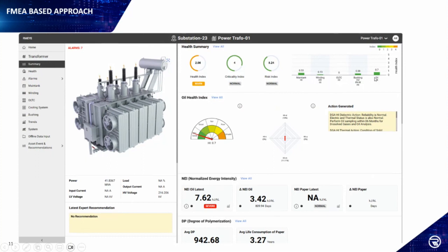The health score of these components is calculated using different parameters. Those parameters I have listed down for the winding, taking it as an example, are the ones we used. Again, this is just one set of parameters. There are other sets of parameters that can also be used for winding health score calculation, like electrical testing, turn ratio testing, and winding resistance testing. All of this electrical testing data can be utilized for winding health score calculation. Similarly, the main tank health score calculation is generally driven by visual inspection as well as offline testing of the electrical asset.